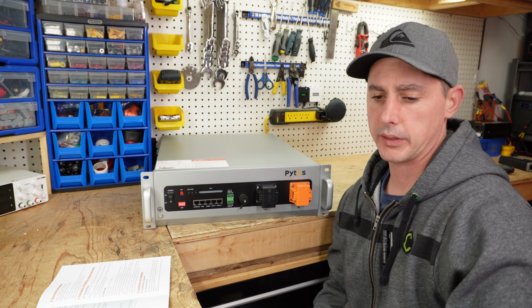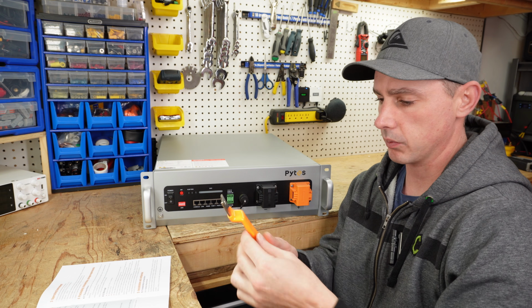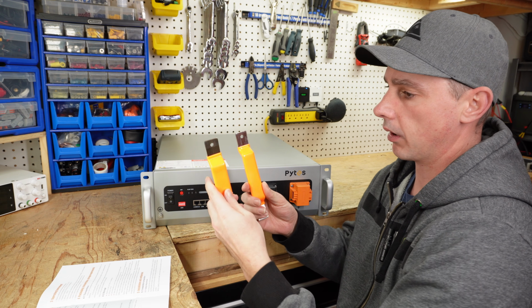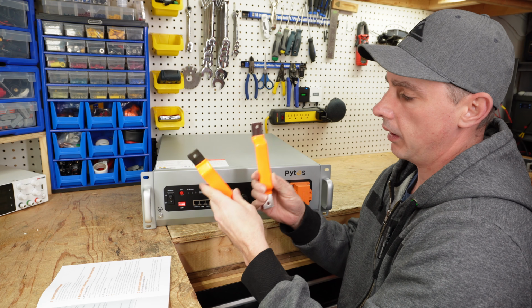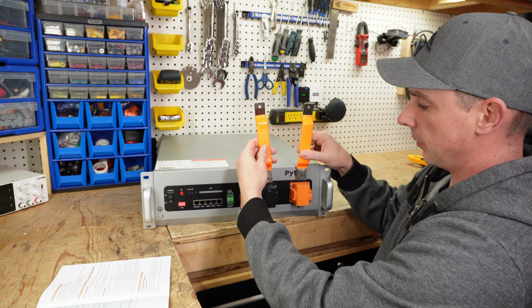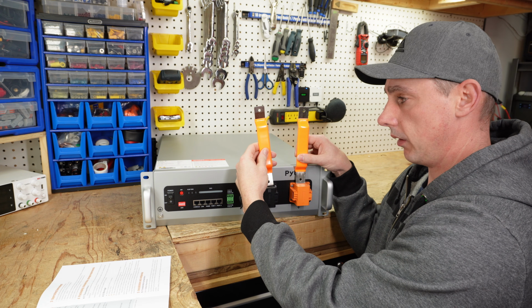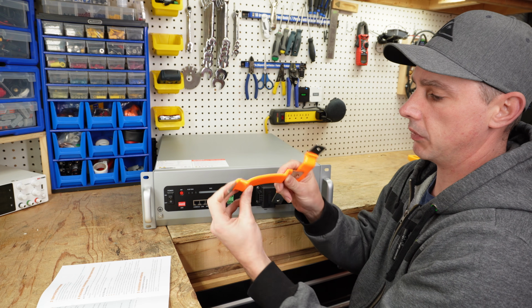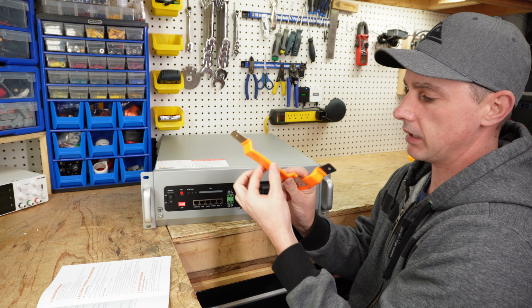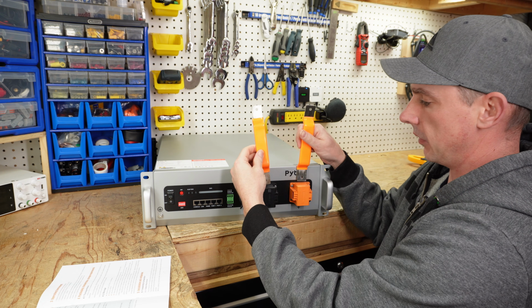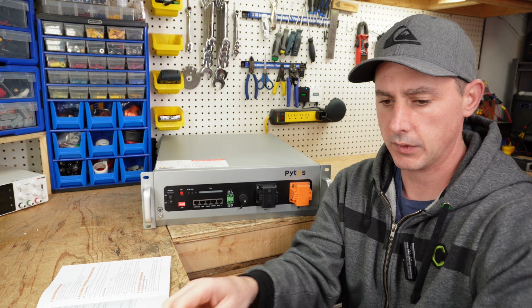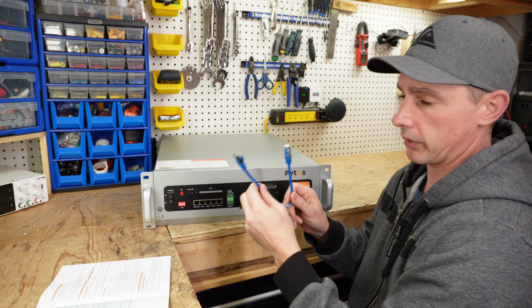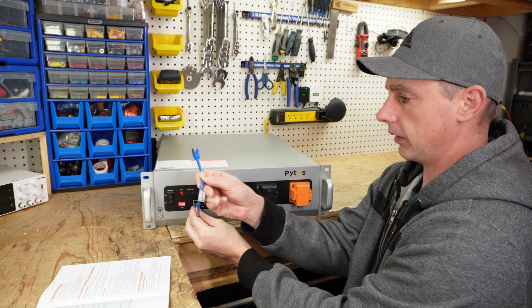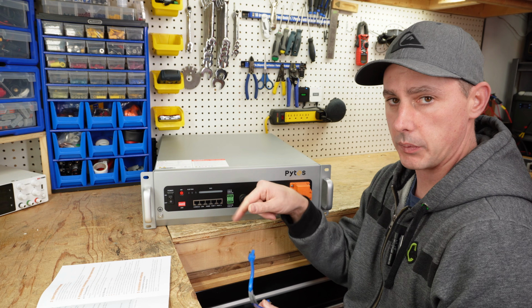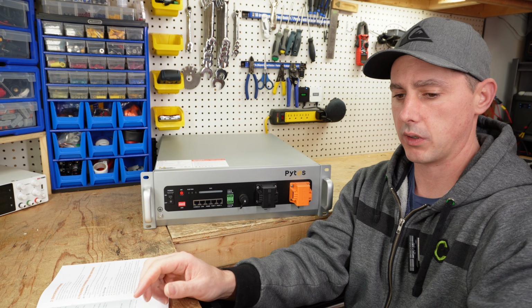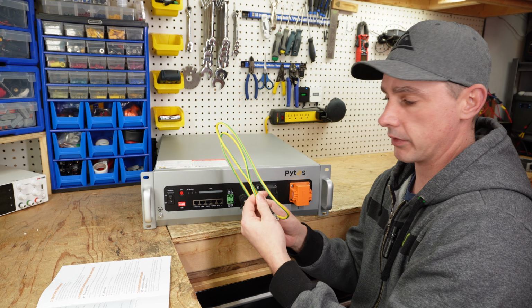Now with this battery in the box, we got these really nice solid copper tin plated bus bars, and these are going to be for connecting multiple units in parallel, and these are flexible and they have a nice heat shrink on them, so these are going to be for parallel connecting. We also have a RJ45 - this is going to be for connecting your modules so that they can communicate with each other, as well as we have a grounding cable for safety.